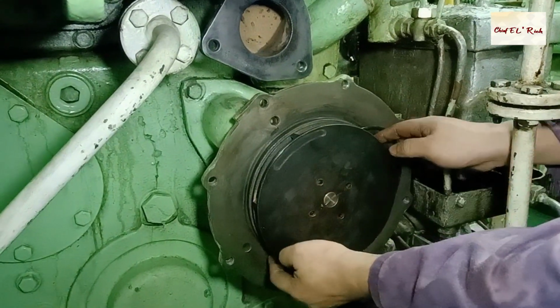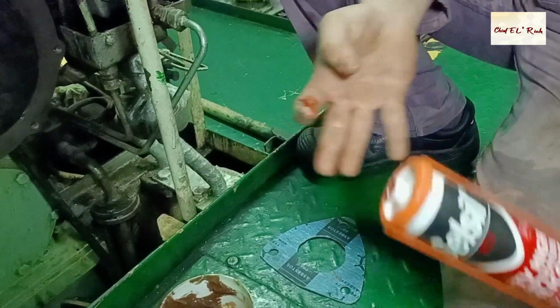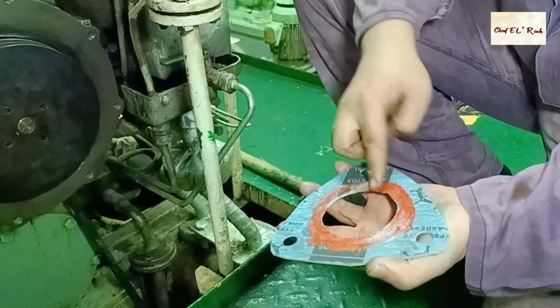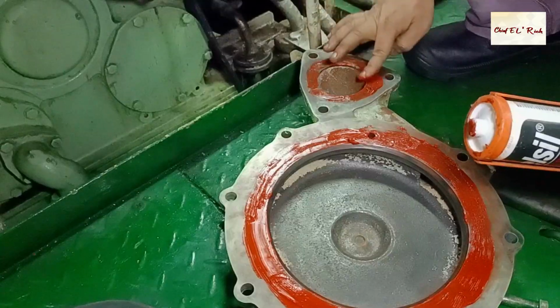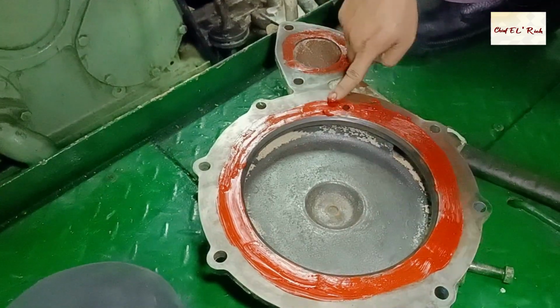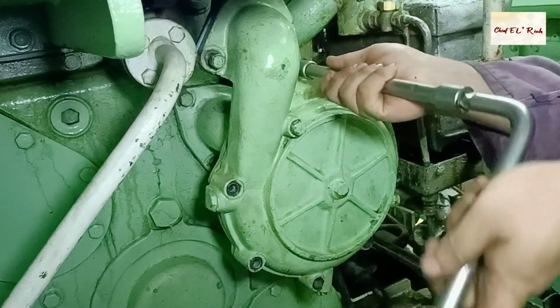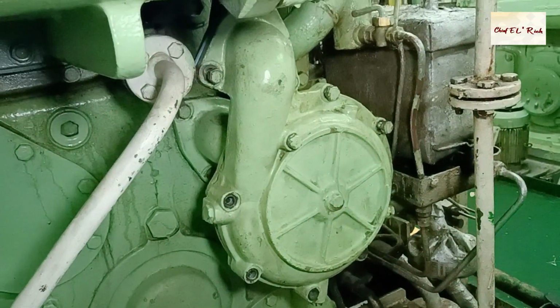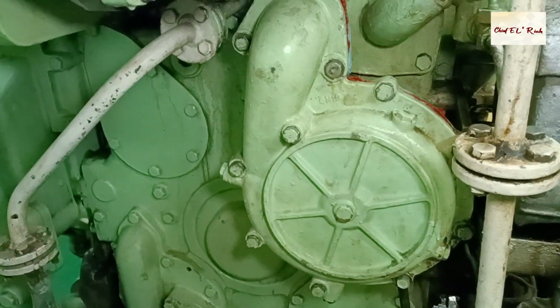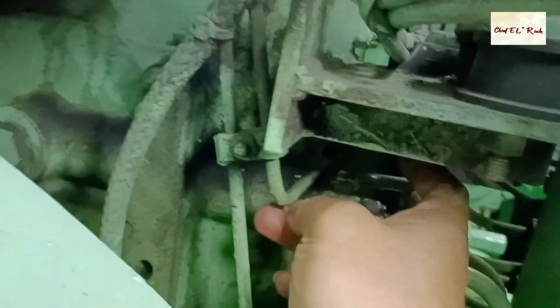Now put the cover O-ring. Install the back cover and gaskets. Put high temperature silicone to prevent water leakages. Tighten the cover bolts in opposite direction and even distances until it is totally sealed. We can now open the cooling water.